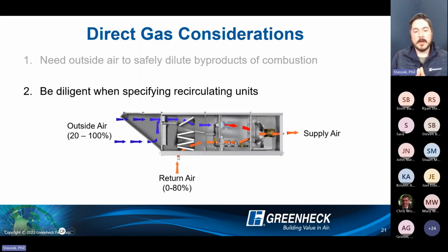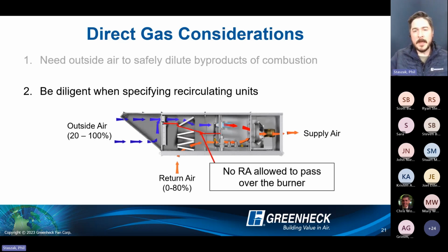Great applications are general manufacturing, warehouse ventilation and warehouse heating, where you're bringing in a minimum of 20% outside air for fresh ventilation at all times, always churning air throughout the facility because the fan is always moving X CFM. It's just a question of what percentage of outdoor air is coming into the building. That only changes when the pressure in the space changes due to an exhaust fan being energized, or, in a warehouse situation, a dock door opening. You lose pressure in the space and it naturally ramps up more outside air, but it's always discharging for whatever discharge temperature you want. And then no return air is allowed to pass across that burner.